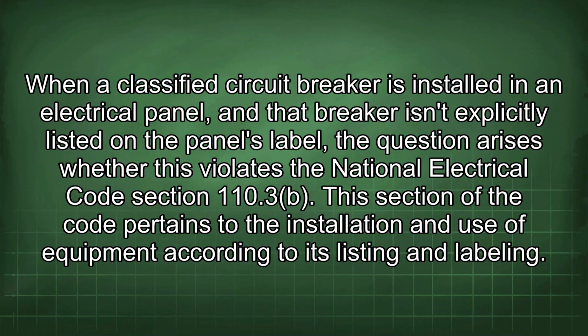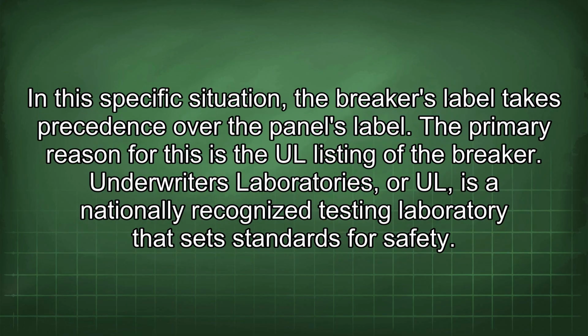When a classified circuit breaker is installed in an electrical panel and that breaker isn't explicitly listed on the panel's label, the question arises whether this violates the National Electrical Code Section 110.3. This section of the code pertains to the installation and use of equipment according to its listing and labeling. In this specific situation, the breaker's label takes precedence over the panel's label. The primary reason for this is the UL listing of the breaker.